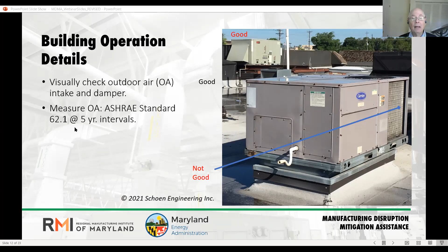And frankly, the other step you want to do, you want to have somebody open the cabinet, stick their head up in this hood, or at least look in the hood with a flashlight, and make sure that during operation, the vanes on the outdoor air damper are actually open. That's what we mean by visually check it. ASHRAE standard 62.1 calls for measuring, actually verifying this by measurement every 5 years. That's not code, and it's not required by law, but it's certainly ASHRAE's recommendation.